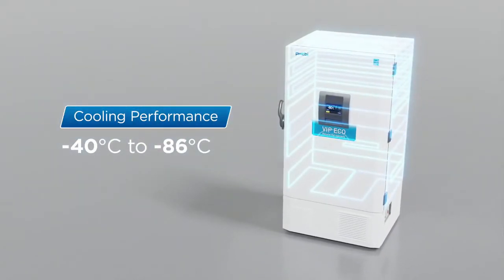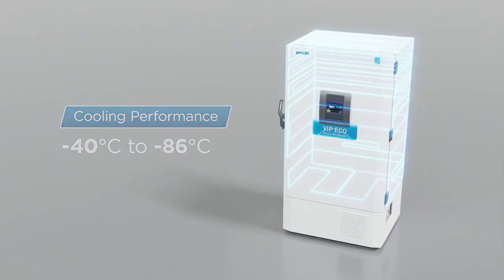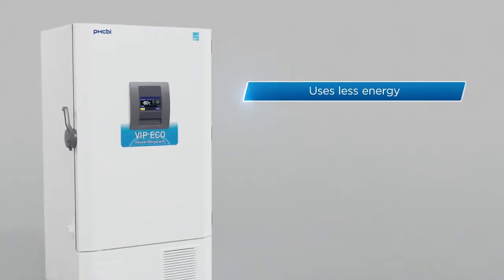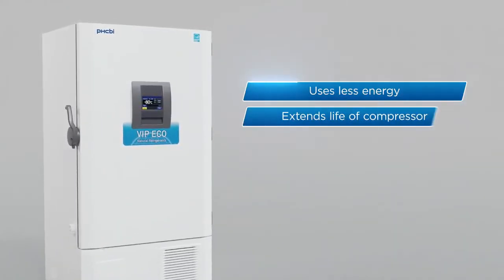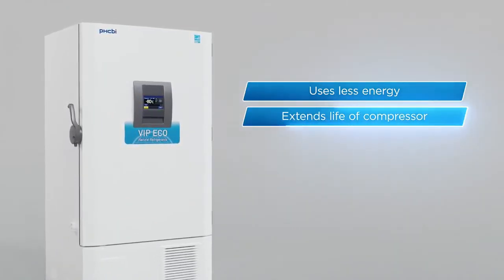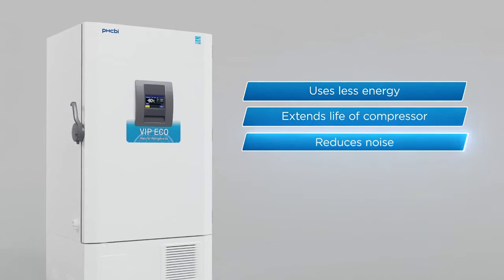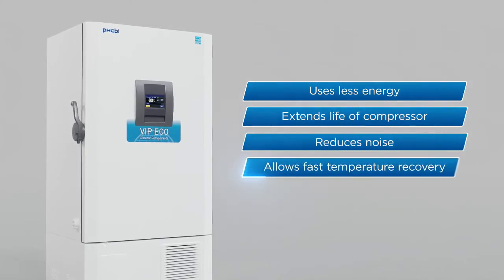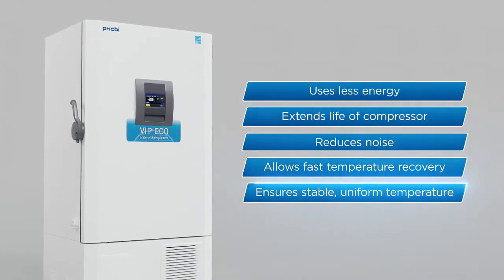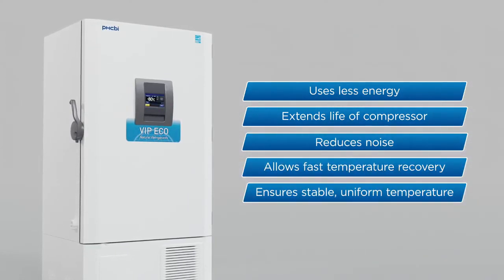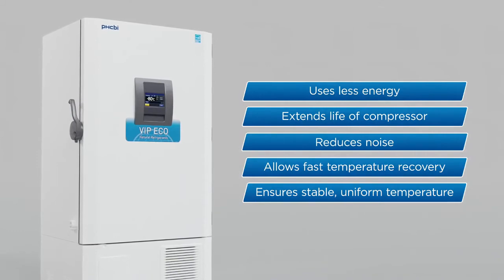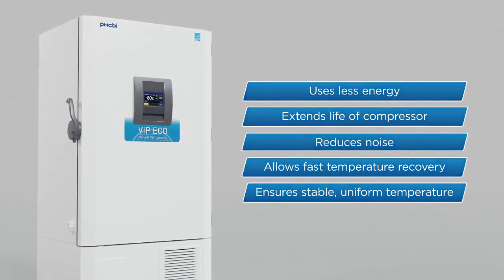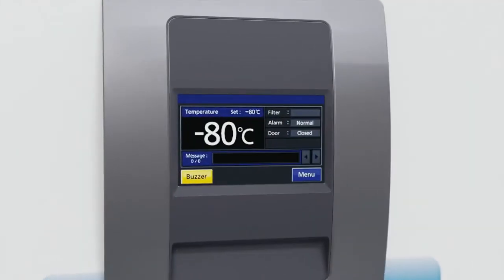Together, the system uses less energy, extends the life of the compressor, reduces noise, allows for fast temperature recovery, and ensures a stable, uniform temperature throughout the freezer regardless of the temperature setting.